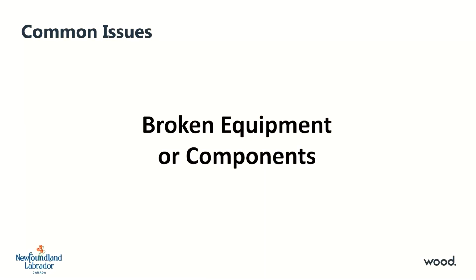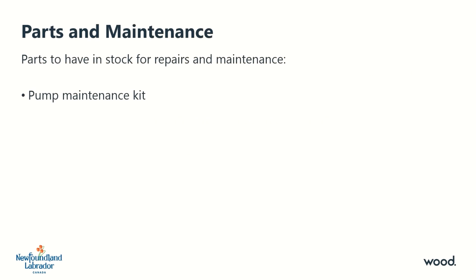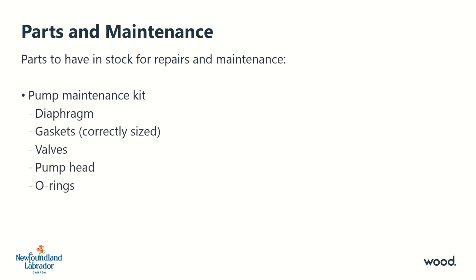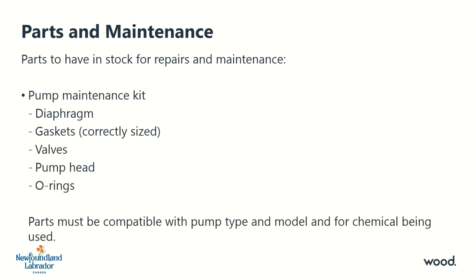Operator trainers and pump suppliers are able to provide some technical expertise to aid in identifying the issues or to help procure replacement components. Before undertaking any maintenance or repair activities, ensure that the proper equipment or replacement parts are available. You should stock a pump maintenance kit, including a diaphragm, appropriately sized gaskets, valves, a pump head, and O-rings. Parts must be compatible with the pump type and model for the chemical that is being used. Many suppliers will offer pump maintenance kits specific to their products.